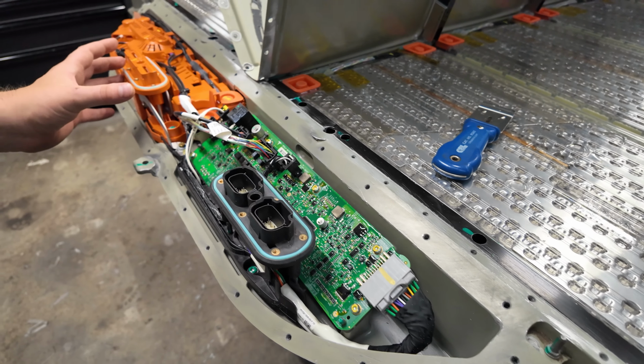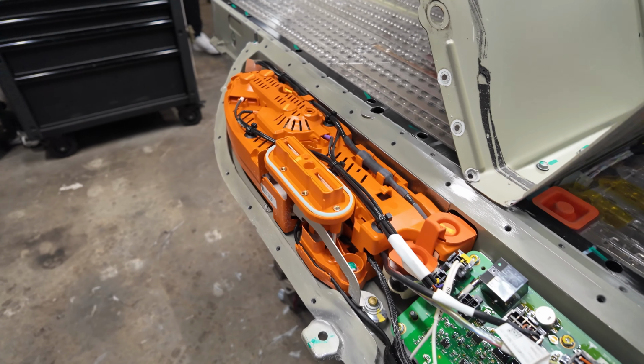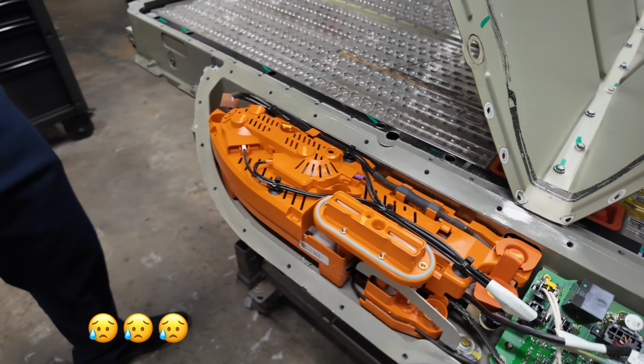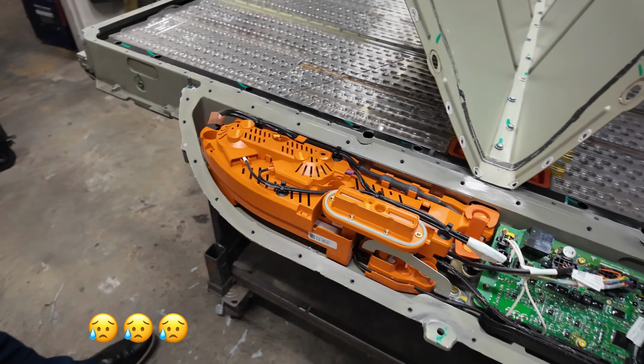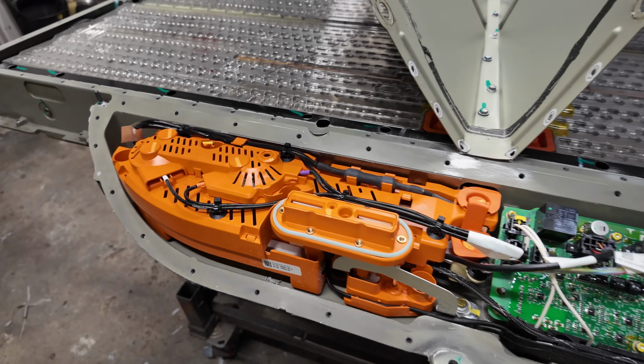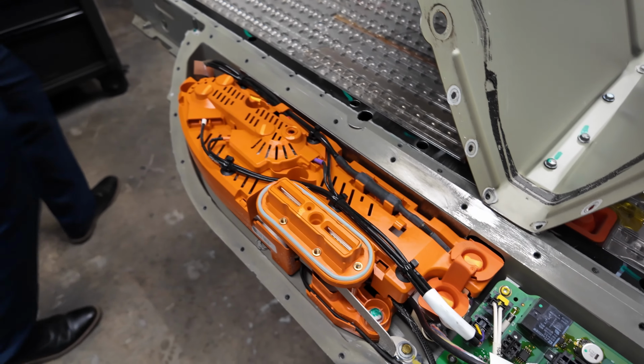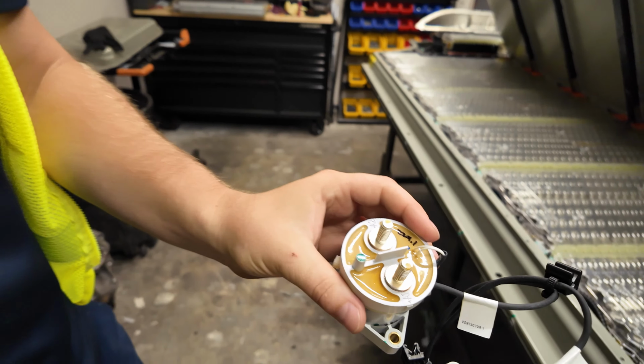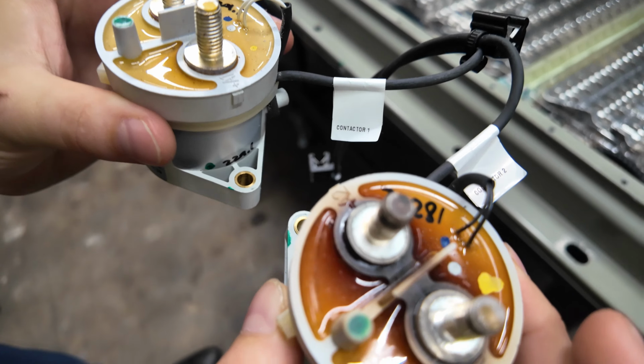We've got contactors here, which a lot of people might already be familiar with. They burn out all the time. That's the thunk, right? Sometimes they thunk when they close? Yes, that, and they weld themselves to each other, they turn black, and you can tell. Here's an example of a burnt contactor versus a non-burnt one.